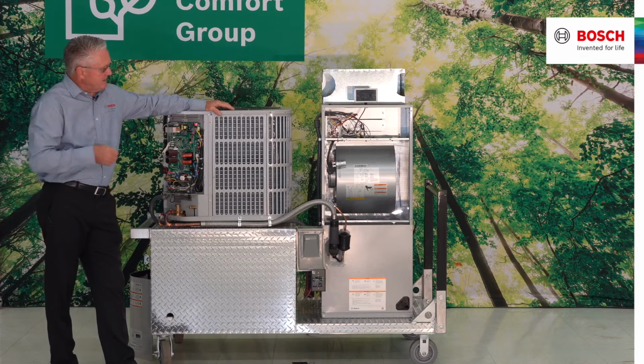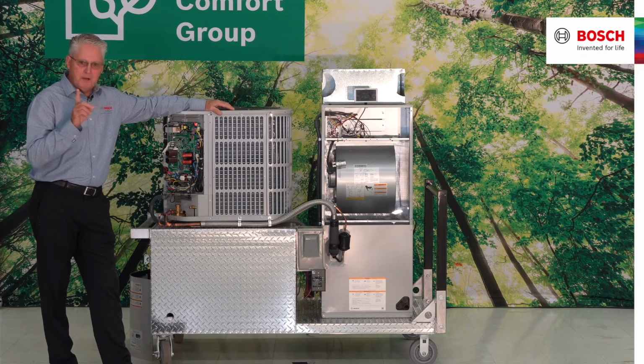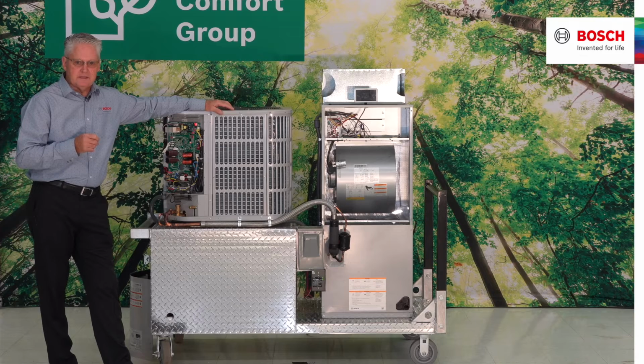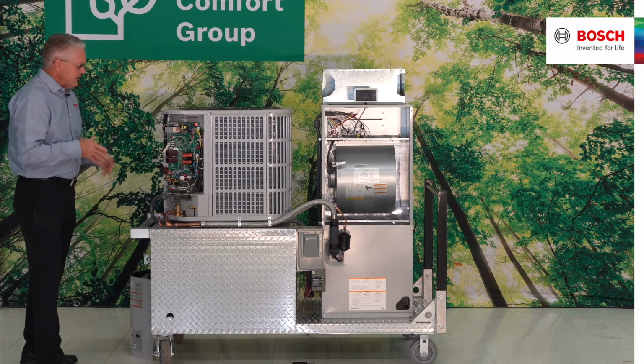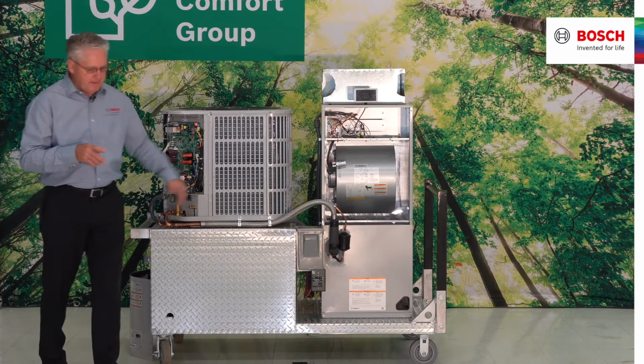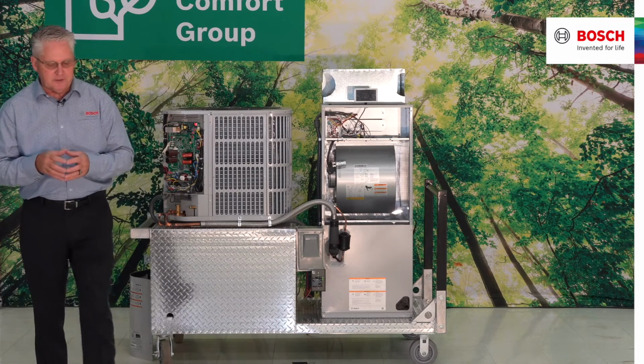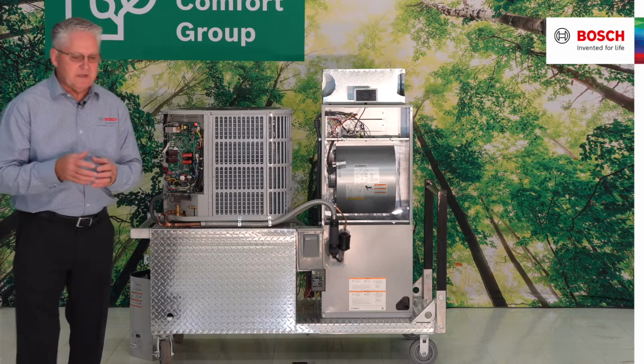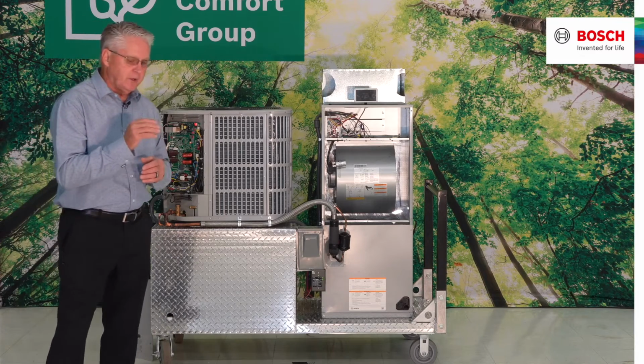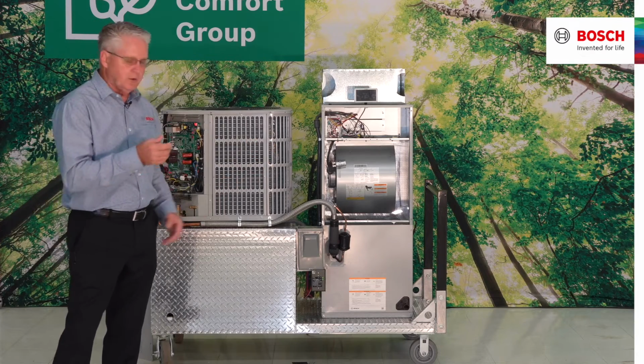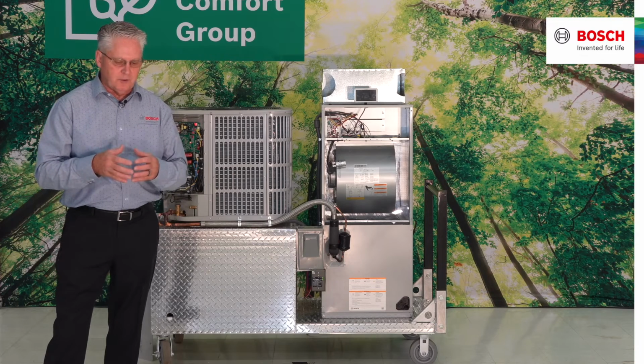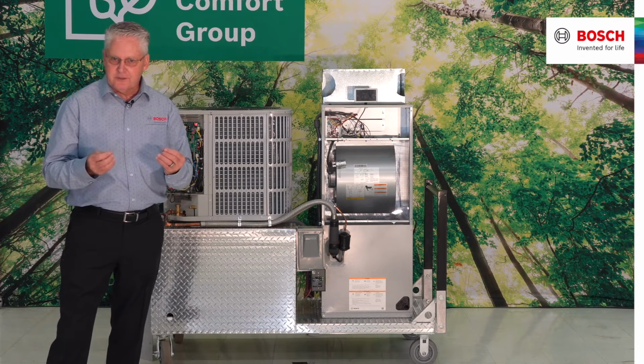But that air handler is not a modular. It is a single piece air handler. On the condensing unit, you may be able to see the hydrophilic material on the coil. We always ask you never to put coil acid on the indoor coil or the outdoor coil. We don't want to get rid of that hydrophilic material.